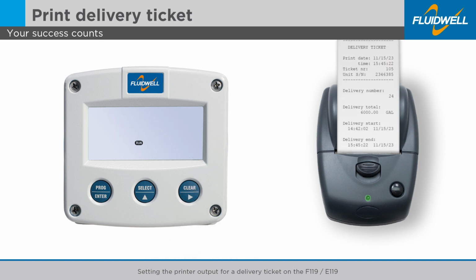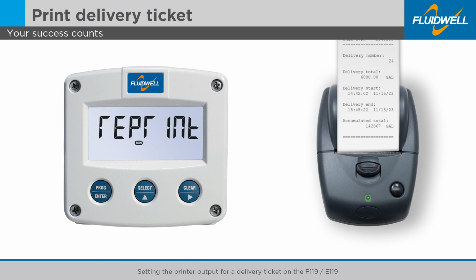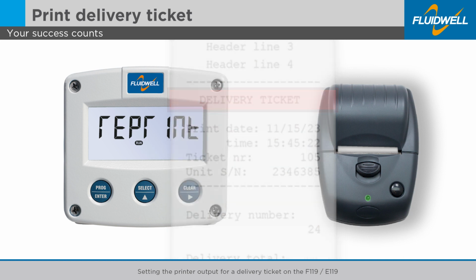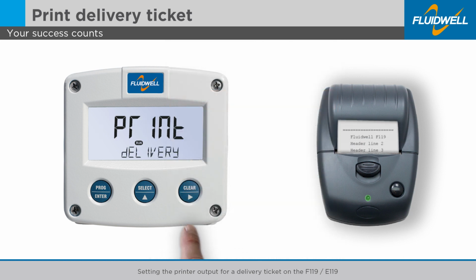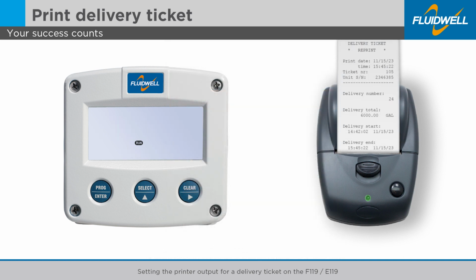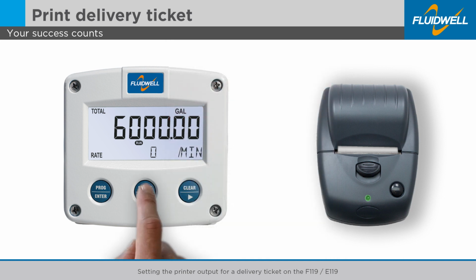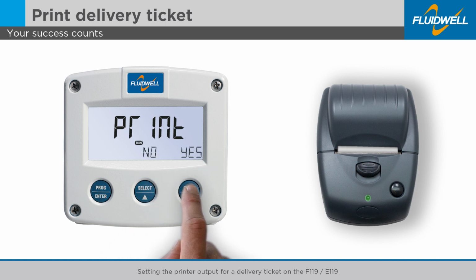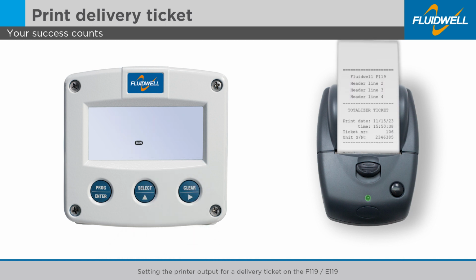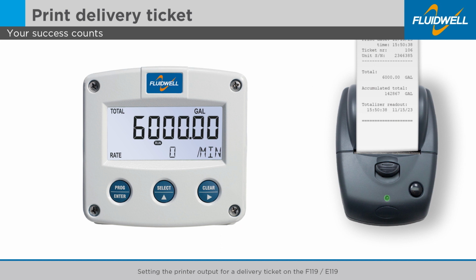This triggers the printing of a delivery ticket, immediately followed by the clearing of the totalizer and the start of a new delivery. Reprints of the last delivery ticket will show Reprint. They can be printed as long as a totalizer ticket is not printed, as that will overwrite the internal ticket data. Besides the delivery tickets, additional totalizer tickets can be printed on demand. This will not clear the totalizer value.